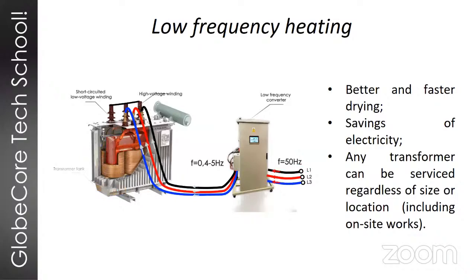So the low frequency heating device is fully automated. It works automatically. It's controlled by PLC under SCADA control. First, before the process begins, the operator inputs all of the data for the transformer, and then the temperature of the windings is controlled periodically to prevent overheating of insulation. The measurements are taken by a special electronic sensor, and there are also additional sensors installed in the transformer tank for redundancy. So we have an absolutely precise measurement of the temperature. When these diagnostic tests are complete, the heating process proper begins automatically and follows an automatic algorithm, an automatic cycle.